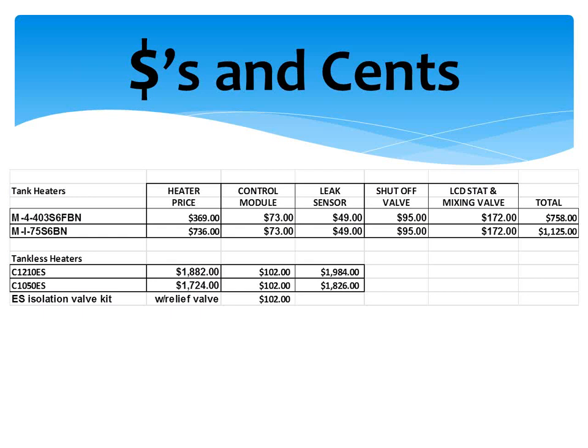Now, the reason most tank water heaters fail is typically multiple things. A tank water heater is basically a steel drum with a glass lining on the inside to protect the steel from the corrosive components of the water. Eventually that glass will crack because something happened, somebody hit it, whatever, and water gets in and starts touching the metal side of the tank. There's an anode rod that goes down inside the tank - he's the sacrificial lamb, his job is to die so your tank doesn't die. People don't check that rod when servicing, and they don't change it out. It's a very common issue.